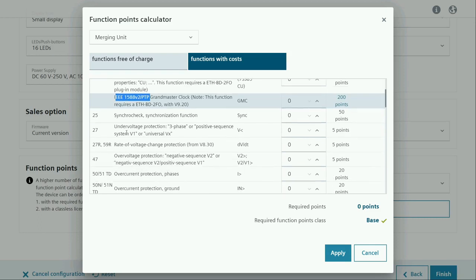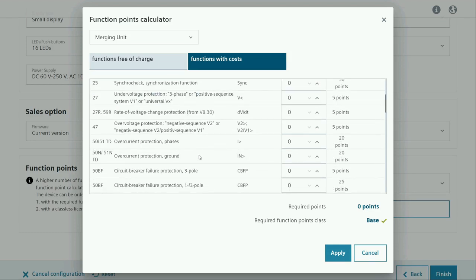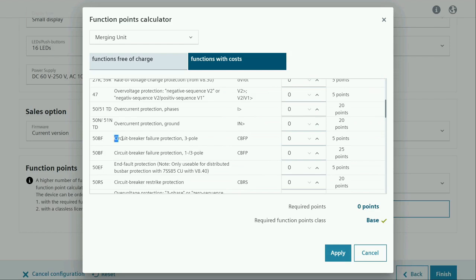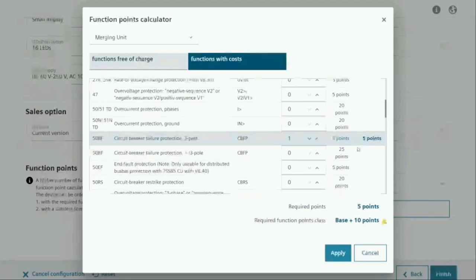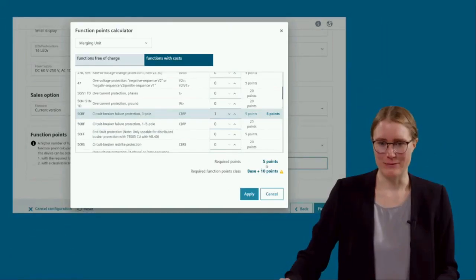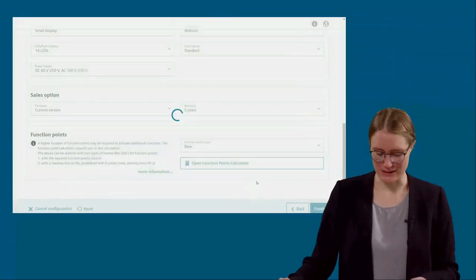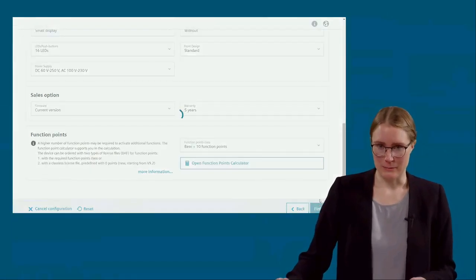Okay, so here, of course, you can select function points for the backup functionality. And in my case, I want to keep my focus on the circuit breaker failure protection. Here I add 5 points for the circuit breaker failure protection. And for those who watch carefully, you may have recognized that the circuit breaker failure protection only costs 5 points in the merging unit. So it is not only interesting to keep the processor load at a lower level, it is also interesting from a financial point of view, because the function points are fewer in the merging unit than in the central unit. Okay, so this would be all we need for the merging unit. We only need 5 points here. So I apply this configuration and we are finished with our merging unit.